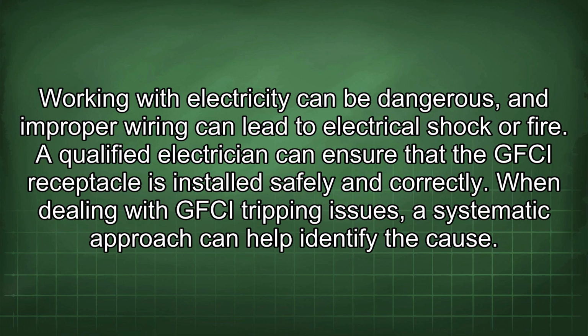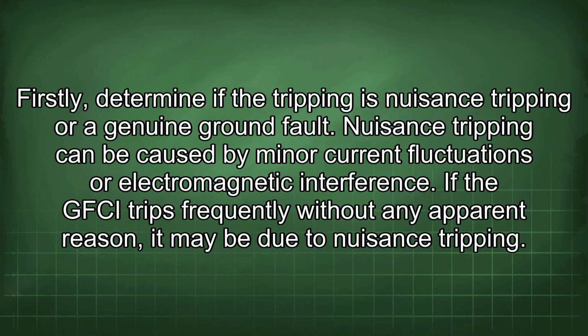When dealing with GFCI tripping issues, a systematic approach can help identify the cause. Firstly, determine if the tripping is nuisance tripping or a genuine ground fault. Nuisance tripping can be caused by minor current fluctuations or electromagnetic interference. If the GFCI trips frequently without any apparent reason, it may be due to nuisance tripping.